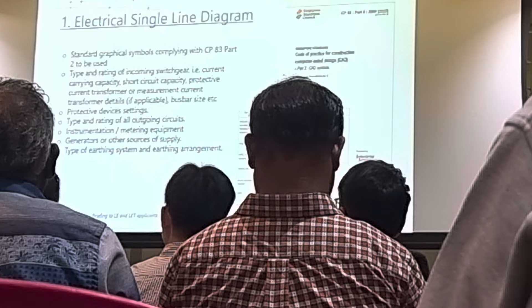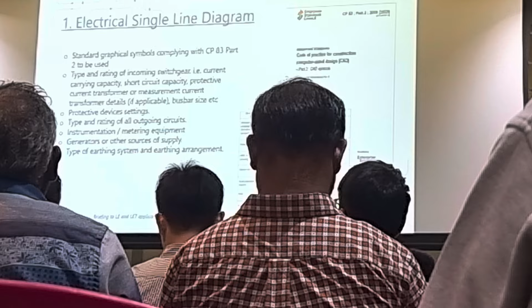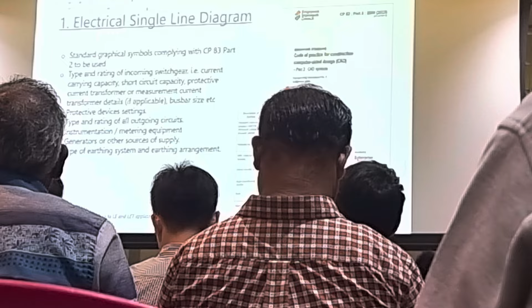Now, finally, the type of earthing. The type of earthing will affect the kind of protective device you use, depending on whether you're using a TNS system or a TT system. In Singapore, we're lucky, we don't have IT, TNCS or other complicated systems, only simple TNS and TT systems. But this is important because the way we design the protective system depends on what kind of earthing system it is.